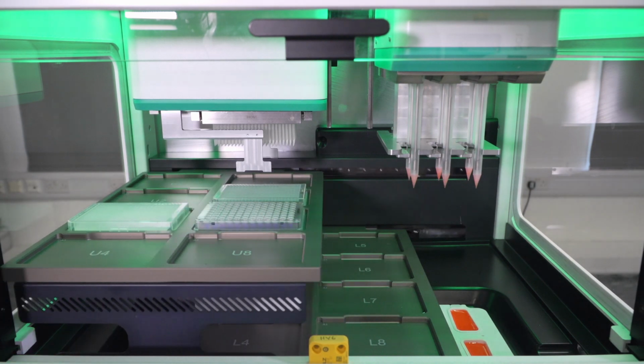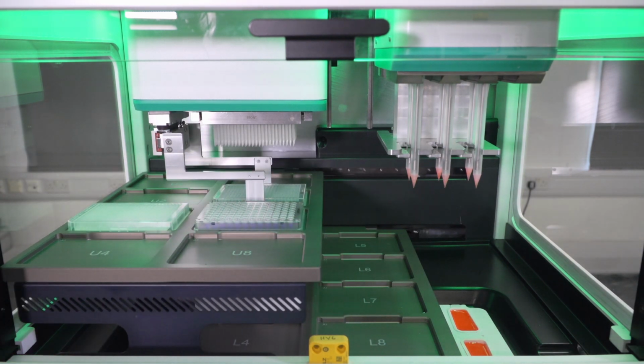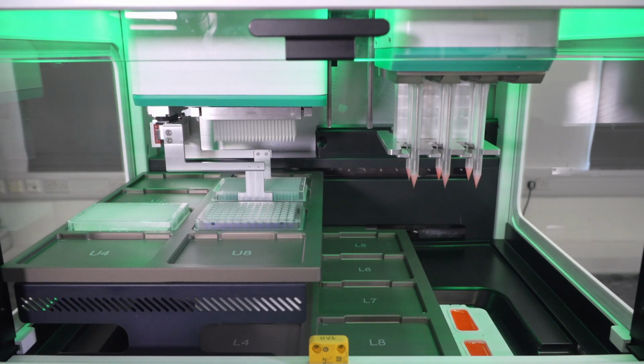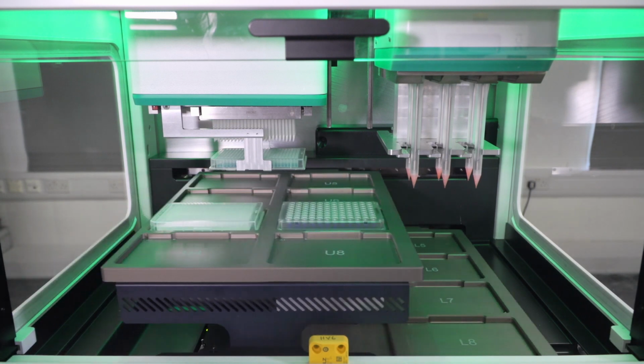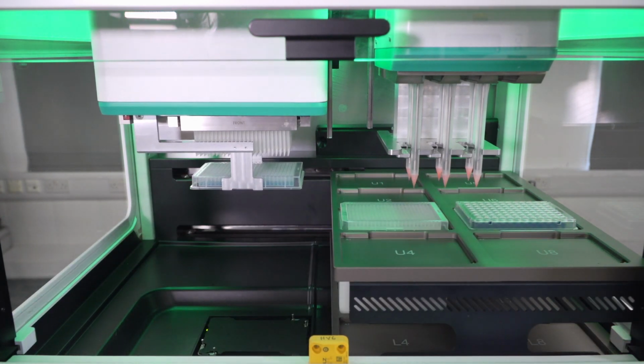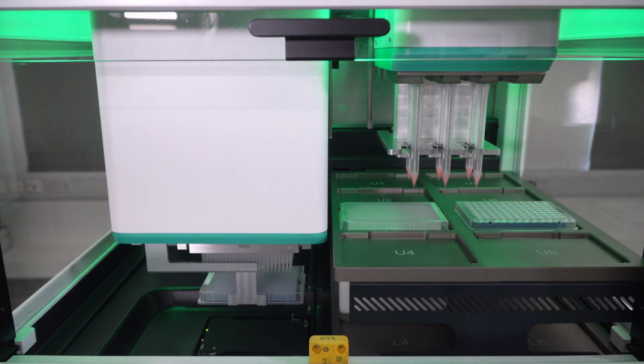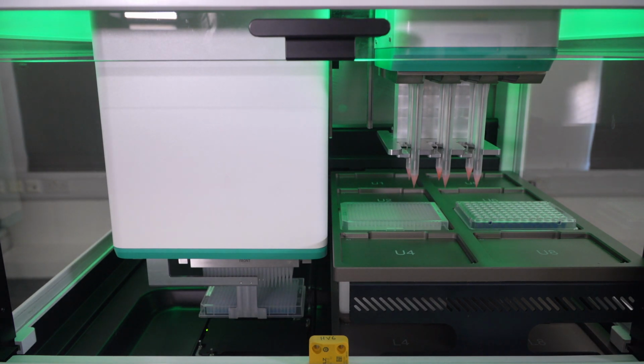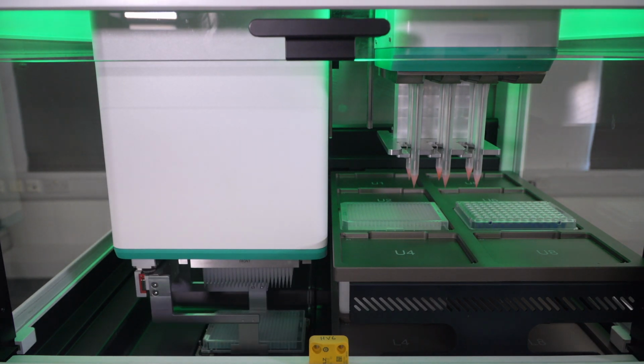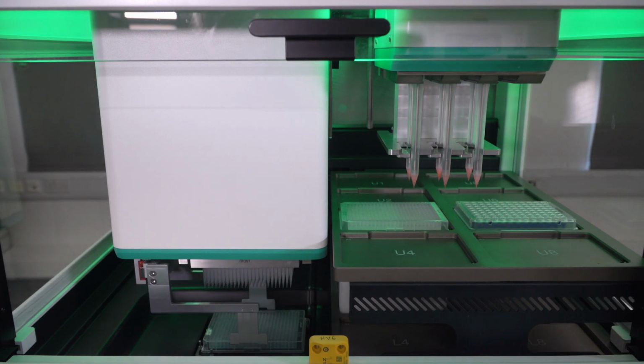So the gripper comes out. It's taking the plate and it's going to take it now down below the moving decks to the shaker position. It does a quick check first, so it first grips and feels the plate, checks that it's there, and then it moves to the shaker position. The shaker is quite a powerful shaker. It works up to 3000 RPM. It's also got a plate lock on it.